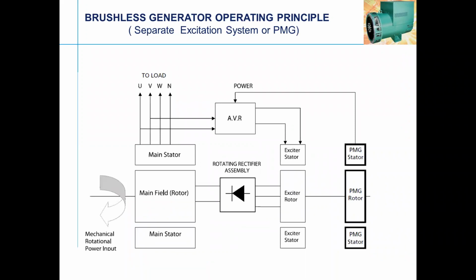Coming to the separate excitation system, which is a 3-machine system, I would say. Fundamentally, it is the same as the previous slide, but you can see a new machine coming in and sitting over here. Earlier you had a main stator, main rotor, exciter stator, and exciter rotor. It was a 2-machine system in the previous one, shunt. Whereas here you have one more machine, a 3-machine system, where the PMG comes in. PMG means permanent magnet generator, where it has its own rotor and a permanent magnet.